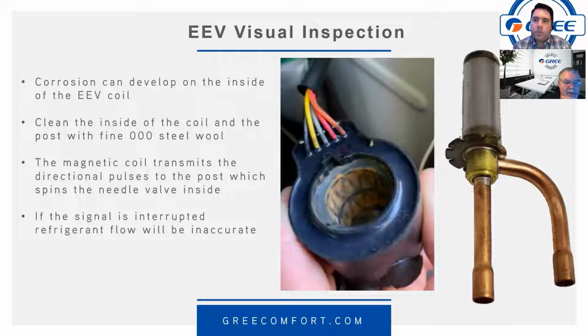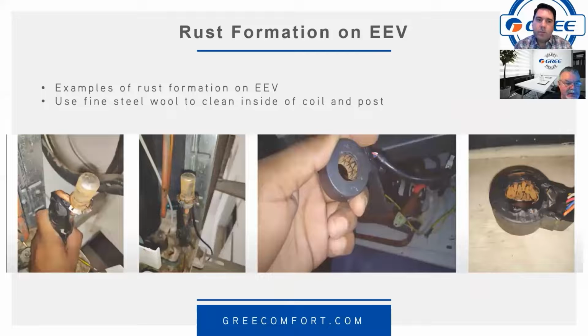The magnetic coil transmits the directional pulses to the post, which spins a needle inside the valve, as we saw in the last slide. If the signal is interrupted, obviously it can cause a problem. Coils are easy to replace. One note on that, after you get it good and cleaned up, Keith, is to use some type of lubricant, just to try to keep corrosion from happening again on it. You can use any type of lubricant and just a thin coat and put it on there.